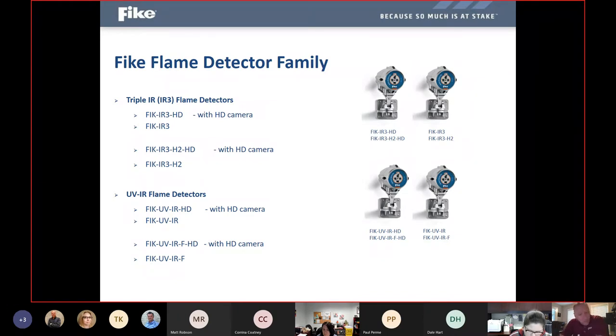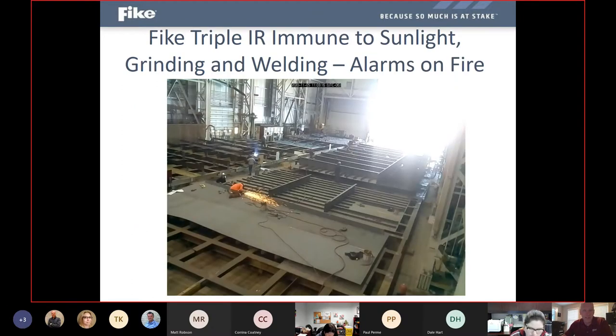Well, now, just by having the HD camera built into these units, anytime it goes into alarm, it immediately stores 60 seconds pre-alarm and 30-second post-alarm history of what was on that HD detector. So you can go out at any time and pull up that exact video and play it and see what put that detector into alarm when it happened. So that, in my opinion, is revolutionary and a great benefit to have from these units. Again, not only to assist in root cause analysis and to determine what failed or happened to initiate the fire, but to show you exactly what it was that set that detector off.